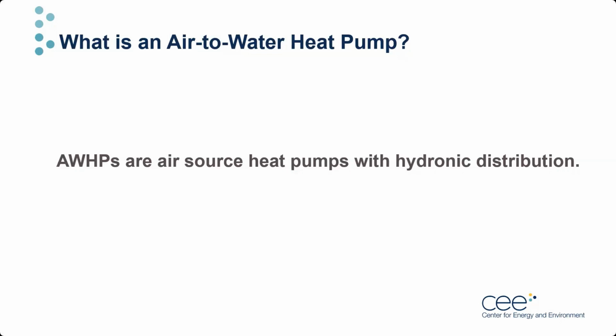Fundamentally, air-to-water heat pumps still extract heat from the ambient air outside the home and move that heat into the home. The only difference is that air-to-air ASHPs use forced air distribution, while air-to-water heat pumps use, you guessed it, water-based distribution. And they distribute that heat via low-temperature radiant systems like in-floor slabs and fan coils, and also through forced air ducted distribution systems and even domestic hot water supply in some cases. So let's have a look at what this looks like as a simple schematic on the next slide.